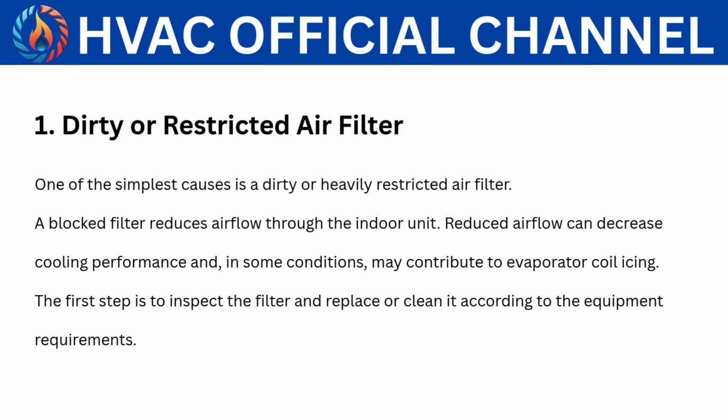Let's get started. 1. Dirty or restricted air filter. One of the simplest causes is a dirty or heavily restricted air filter. A blocked filter reduces airflow through the indoor unit. Reduced airflow can decrease cooling performance and in some conditions may contribute to evaporator coil icing. The first step is to inspect the filter and replace or clean it according to the equipment requirements.